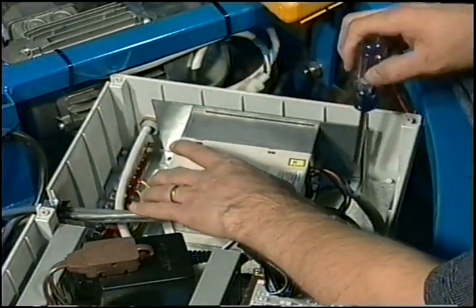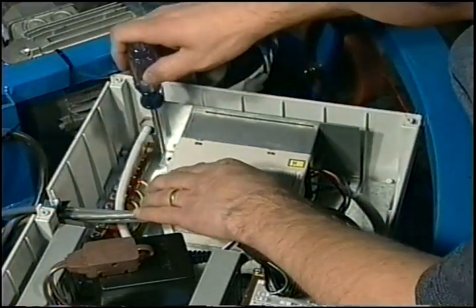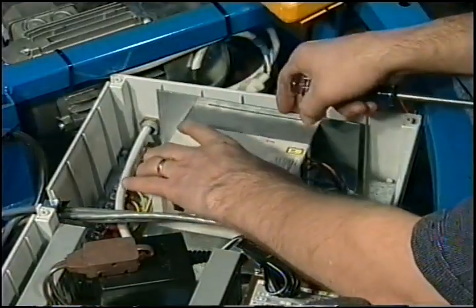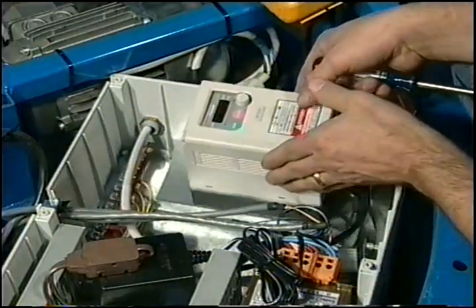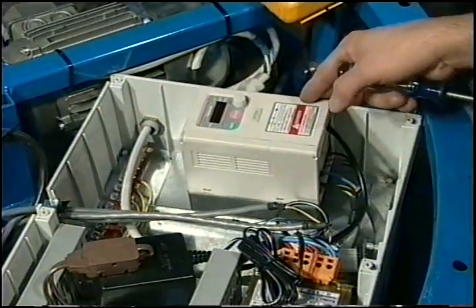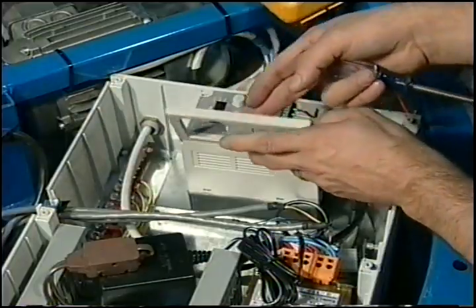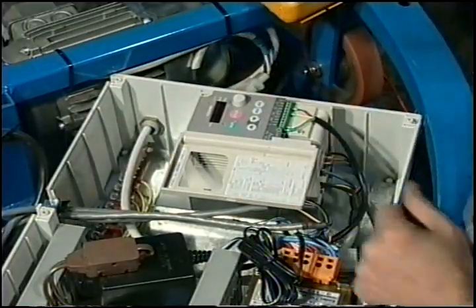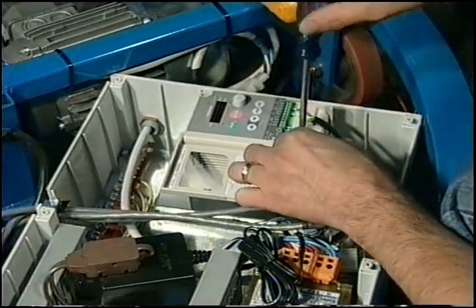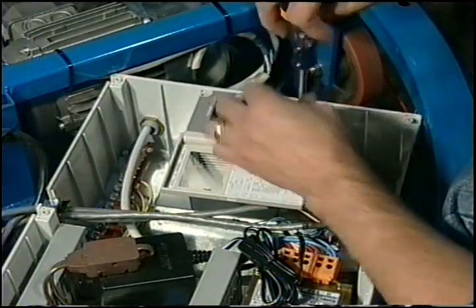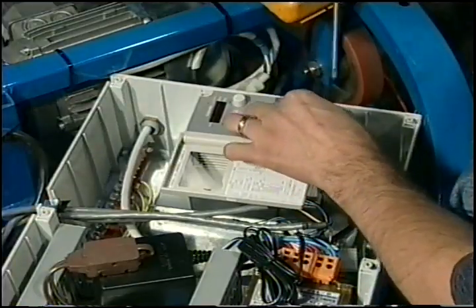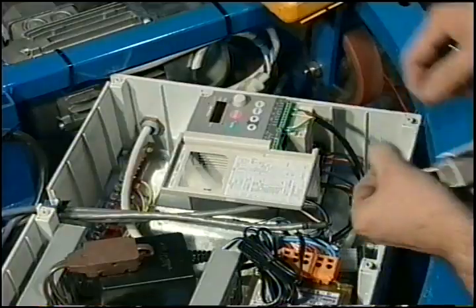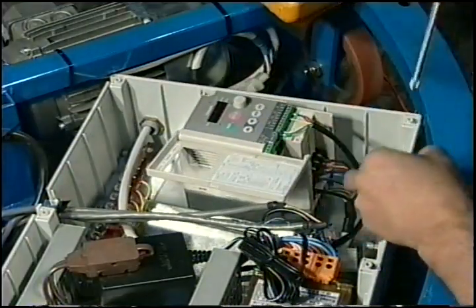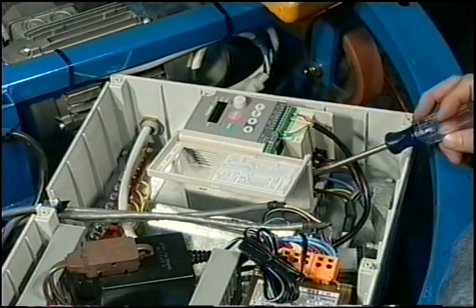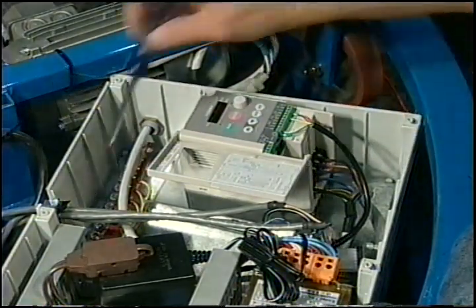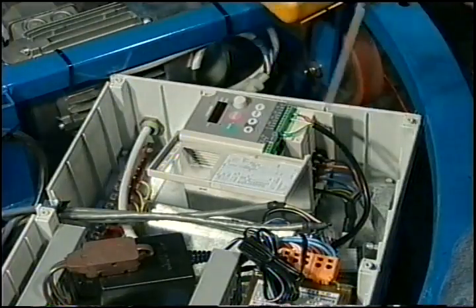To look at this more closely, you can remove these 2 screws here and here. And once you do that, you're able to lift this up, and you have a little access panel door that you open up from the side. Once you open that up, you have another little panel here that has a screw in it, which you can open. And once you open that up, you're able to see the main power coming into it. This terminal right up here on the top is your earth ground. It's tied into your earth ground terminal here.